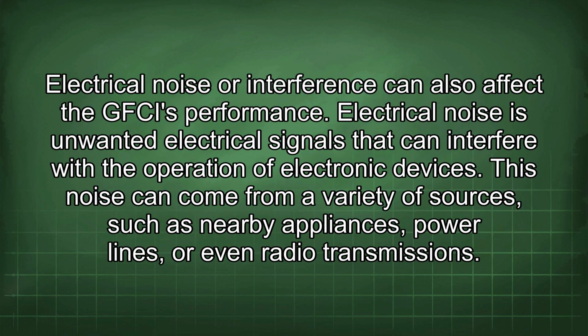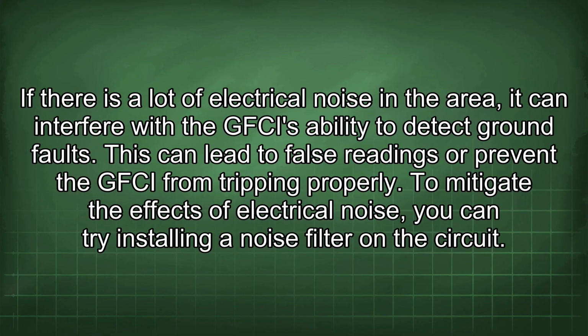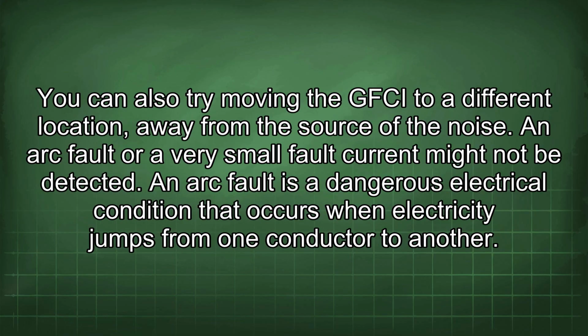Electrical noise or interference can also affect the GFCI's performance. Electrical noise is unwanted electrical signals that can interfere with the operation of electronic devices. This noise can come from a variety of sources, such as nearby appliances, power lines, or even radio transmissions. If there is a lot of electrical noise in the area, it can interfere with the GFCI's ability to detect ground faults. This can lead to false readings or prevent the GFCI from tripping properly. To mitigate the effects of electrical noise, you can try installing a noise filter in the circuit. You can also try moving the GFCI to a different location away from the source of the noise.